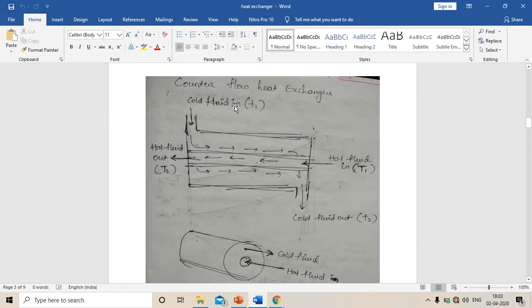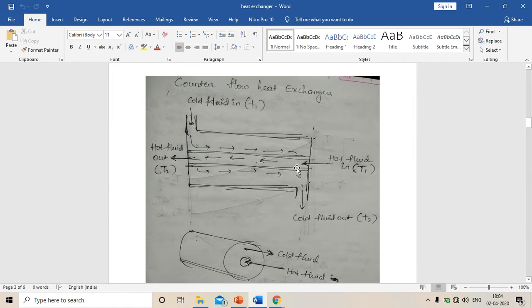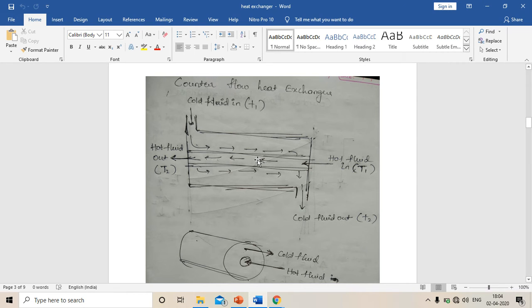One more type is the counter flow heat exchanger. Here, cold fluid enters from the left side flowing right, and hot fluid flows from right to left — so the direction of flow is opposite. Because of this, the temperature difference between hot and cold fluid remains nearly the same throughout the heat exchanger, which increases its effectiveness. As we know, temperature difference is one of the most important parameters for heat transfer rate.